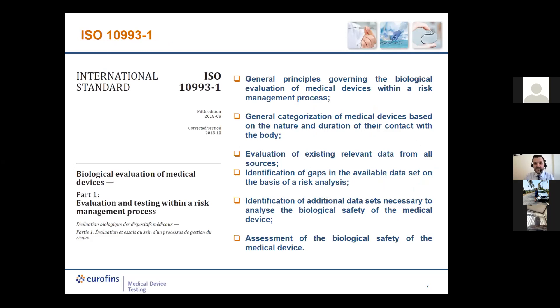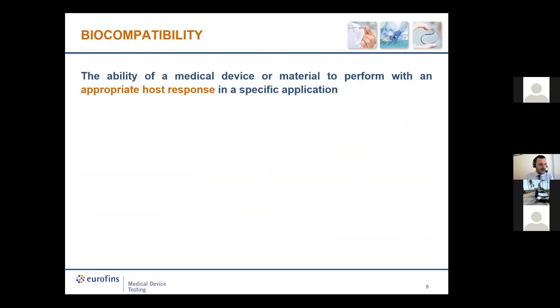The ISO approach has evolved from the first edition of 1992 — 'Guidance on Selection of Tests' — to the fifth, current edition: 'Evaluation and Testing within a Risk Management Process.' ISO 10993-1 specifies the general principles governing biological evaluation of medical devices within a risk management process: the general categorization of devices based on nature and duration of contact with the body; evaluation of existing relevant data from all sources; identification of gaps in the available data set; identification of additional data necessary to analyze biological safety; and finally, assessment of the biological safety of the medical device.